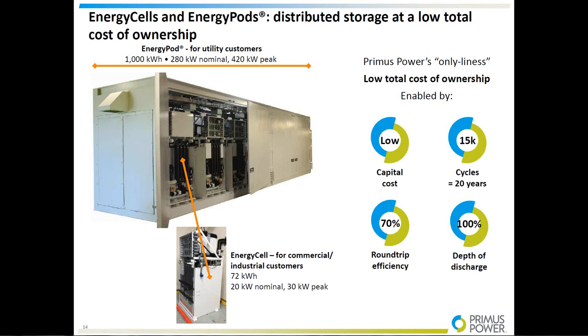The modularity is a key highlight of the product. The 40-foot shipping container discharges up to 420 kilowatts. Inside are 14 flow battery cells, which are themselves a product we are selling. Individual cells can be discharged up to 30 kilowatts DC for the full duration — a 72 kilowatt-hour cell. Those cells can be placed in shipping containers or taken out and put in strings for buildings. There are many different ways to deploy these batteries, giving customers opportunities for site-specific deployments.